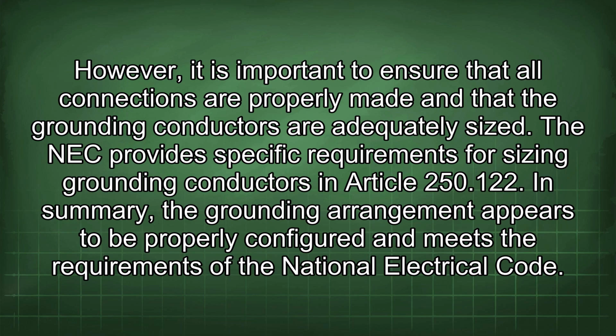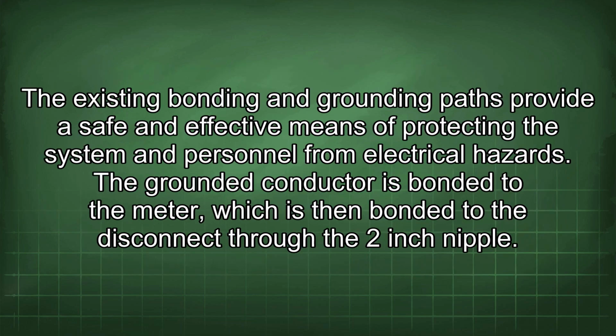However, it is important to ensure that all connections are properly made and that the grounding conductors are adequately sized. The NEC provides specific requirements for sizing grounding conductors in Article 250.122. In summary, the grounding arrangement appears to be properly configured and meets the requirements of the National Electrical Code. The existing bonding and grounding paths provide a safe and effective means of protecting the system and personnel from electrical hazards. The grounded conductor is bonded to the meter, which is then bonded to the disconnect through the 2-inch nipple.